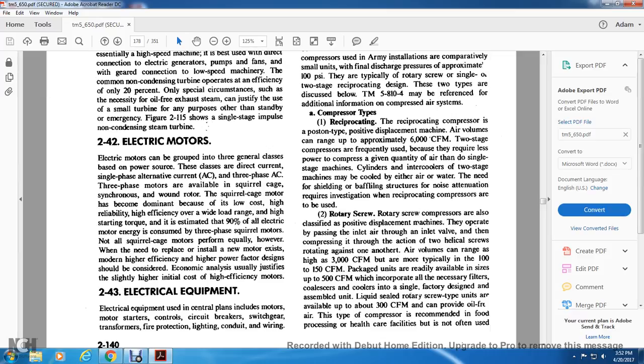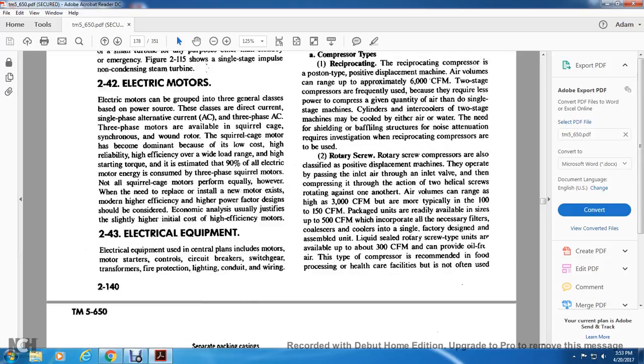Rotary screw. Rotary screw compressors are also classified as positive displacement machines. They operate by passing inlet air through the inlet valve, then compressing it through the action of two helical screws rotating against one another. Air volumes can range up to a high of 3,000 CFM, but are typically about 150 CFM. Packaged units are readily available in sizes up to 500 CFM, incorporating the necessary filters, coalescers, and coolers, factory designed and assembled. Liquid-sealed rotary screw units are available up to about 300 CFM to provide oil-free air. This type of compressor is recommended for food processing and healthcare facilities.